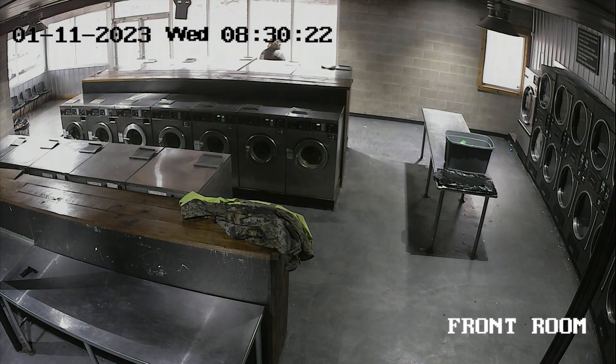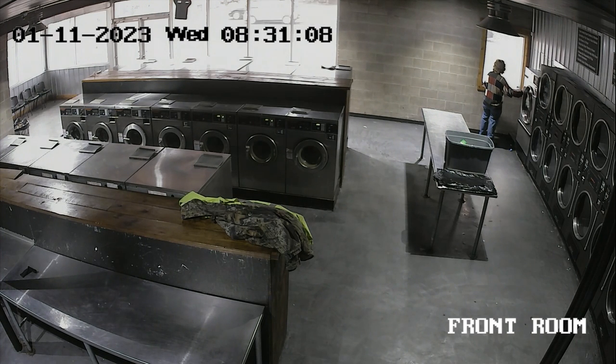I have been here numerous times and seen these dryers turning so loaded that the door's popping open. What happens is your exhaust fan cannot get the heat in the center of that dryer out fast enough, so it builds up more and more heat while the machine is still pumping more heat in.